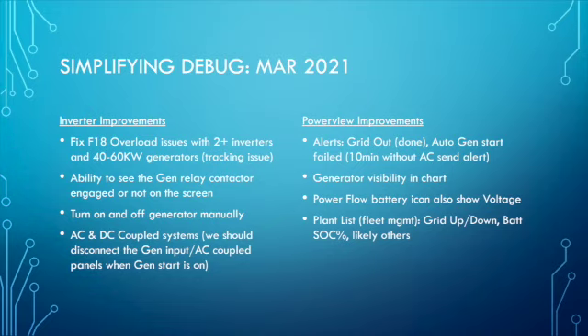Also, the ability to turn on and off the generator manually via the 2-wire start on the system. And then the last thing is when we AC and DC couple systems, the AC side is especially problematic because if we're using a generator, we are locked to that generator frequency. We can't control the frequency of the inverter, so it doesn't allow us to control the AC coupled panels like we should, and so it can lead to overcharging. So what we're doing is if you wire the AC coupled panels into the gen input, then we can disconnect that gen input if the generator is running.